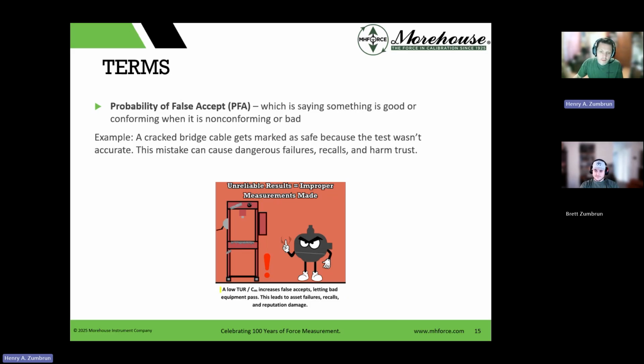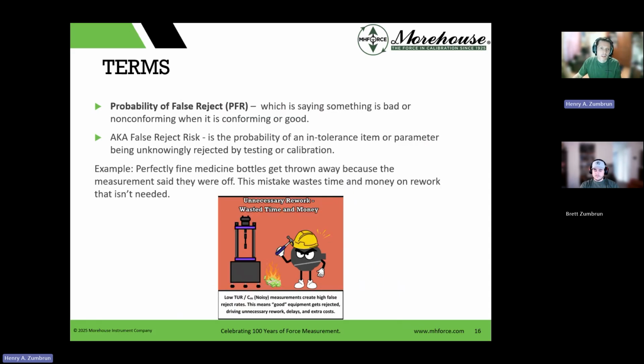Down here, we're going to talk about this later. A low TUR/CM. TUR is test uncertainty ratio, and CM is measurement process capability. The reason CM is listed there is because JCGM 106 says TUR is such a butchered term that we should start talking about CM, measurement process capability. Probability of false reject means saying something is bad or non-conforming when it is conforming or good. Also known as false reject risk, it is the probability of an in-tolerance item or parameter being unknowingly rejected by testing or calibration. This is the title of this slide and what we're talking about.